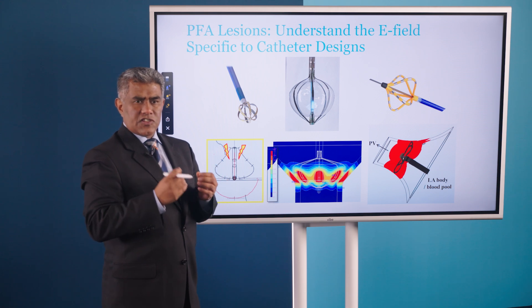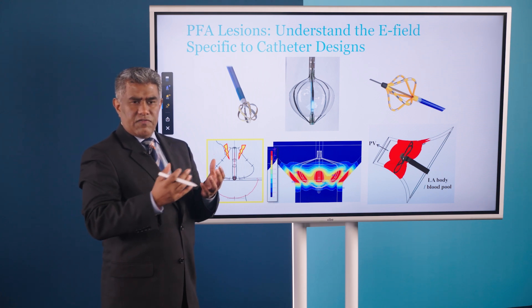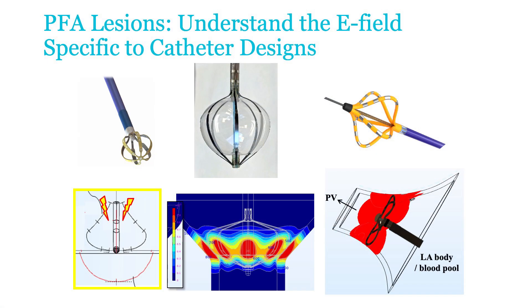To really understand what a PFA lesion is, it's critical to understand the electric field, which as you can tell from the slide, is very specific to each catheter design. Every electric field is generated by the voltage applied from the PFA generator. I'm going to start off by talking about focal catheters.